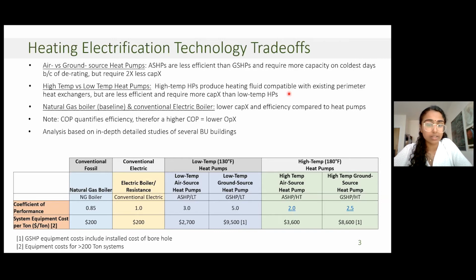The other trade-off you can look at is between high temperature and low temperature heat pumps. High temperature heat pumps have heating fluids that are more compatible with existing perimeter heat exchangers, so between the 170 and 180 degree Fahrenheit range, but are also less efficient and require more capital than a low temperature heat pump. And as we've mentioned earlier, these heat pumps are less proven in the market. And so you're going to find smaller sizes or systems that are more in the validation phase. So what you can notice here is that there's certain trade-offs that we can take advantage of. The fact that the heat pump systems have a higher efficiency, but also a higher cost, and that boiler systems are less expensive, but also less efficient. So that's something we'll be looking at in the presentation moving forward.